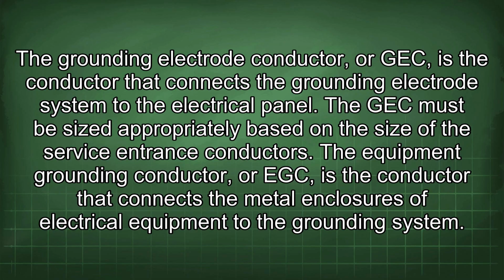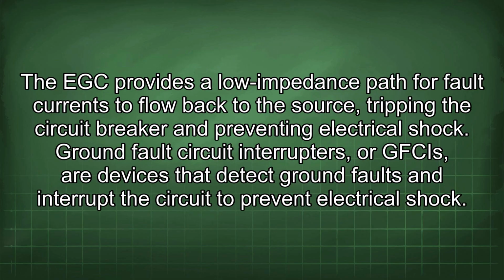The equipment grounding conductor, or EGC, is the conductor that connects the metal enclosures of electrical equipment to the grounding system. The EGC provides a low impedance path for fault currents to flow back to the source, tripping the circuit breaker and preventing electrical shock.